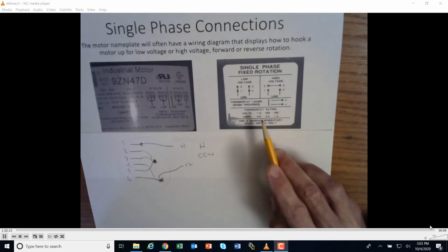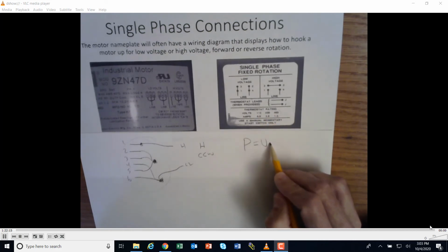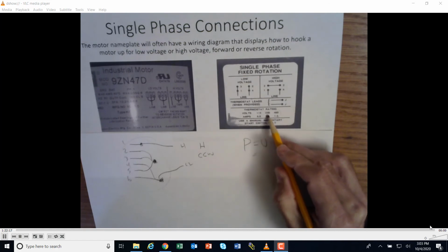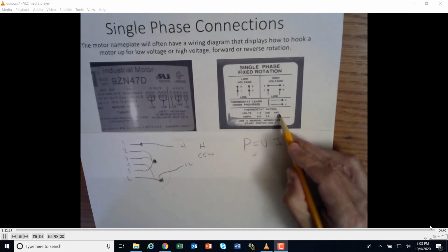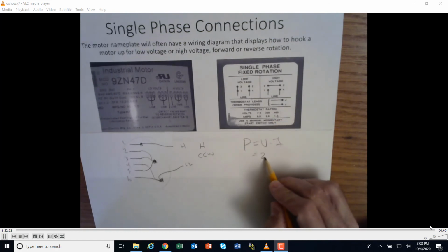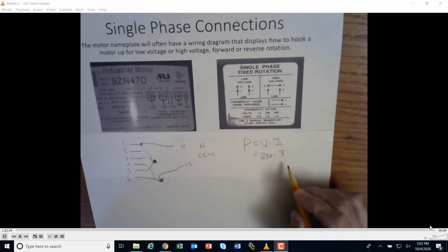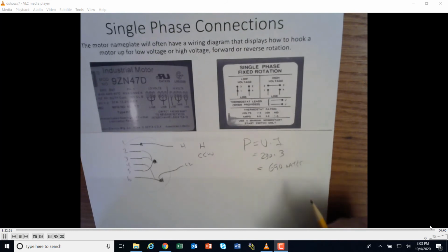So just understanding that power is equal to V times I, I'm gonna just pick any one of these. I can pick 230 times 3. Okay. And if you get 230 times 3, you get 690 watts. Okay. Now, we know that 1 horsepower equals about 750 watts. So you can tell that this is close to a 1 horsepower, just under a 1 horsepower motor.